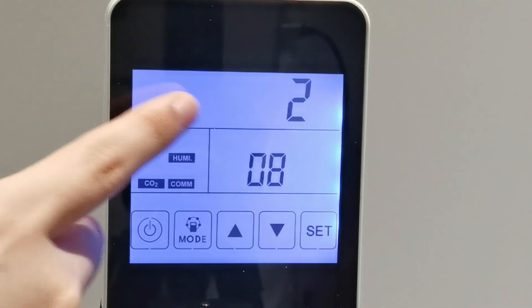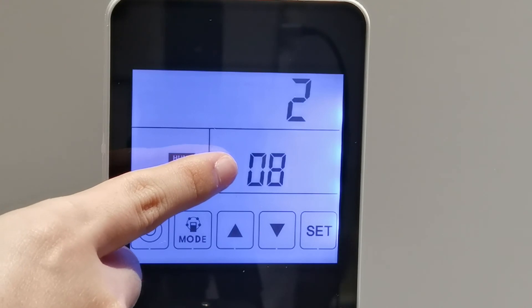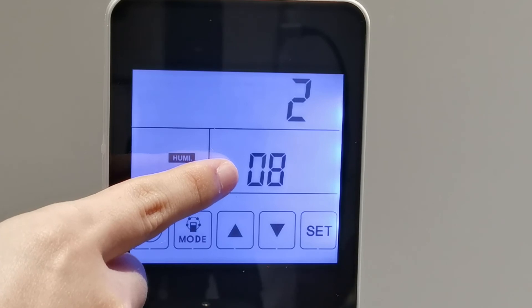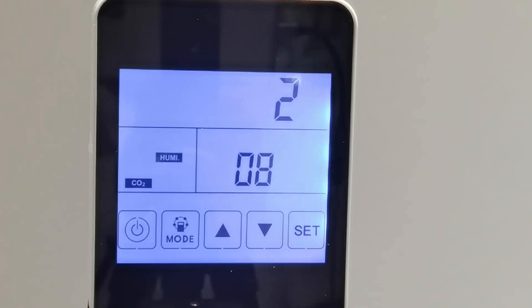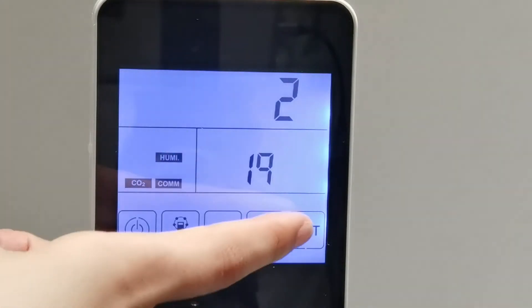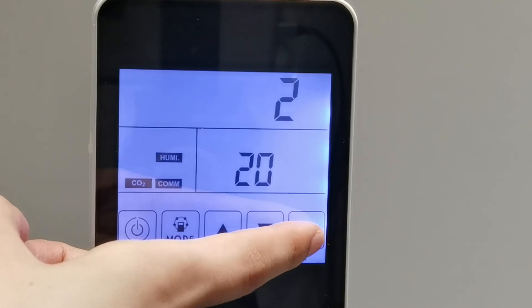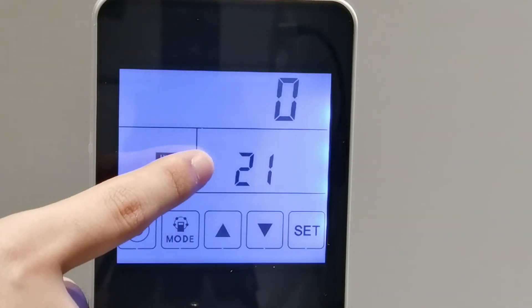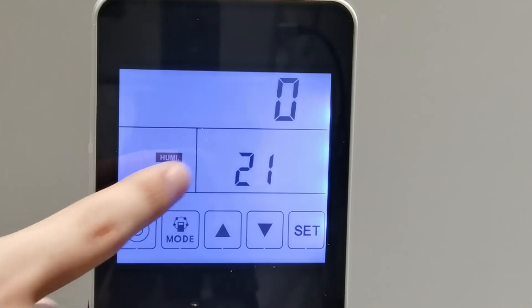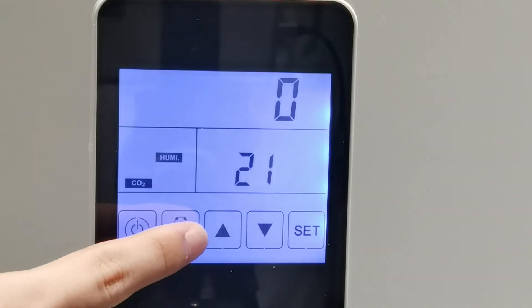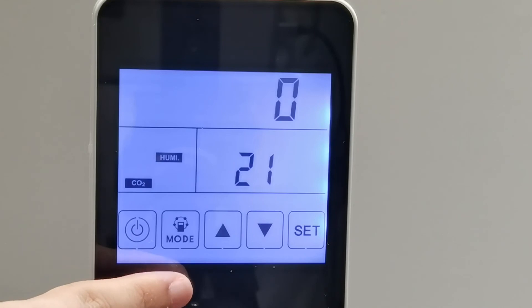Parameter 08 refers to the central control function to identify the address of the ERV. Parameters 19 and 20 are empty. Parameter 21 refers to matching the suitable program on the PCB board to the ERV model — different models have different codes.